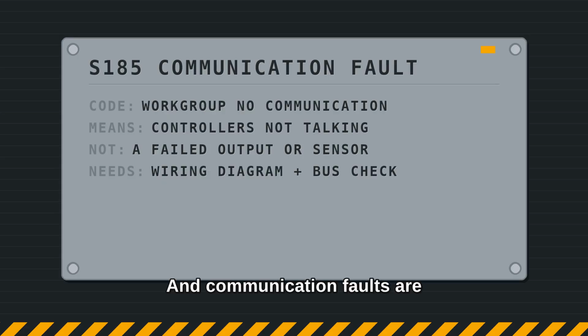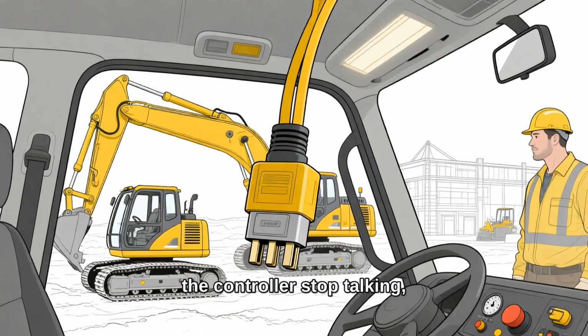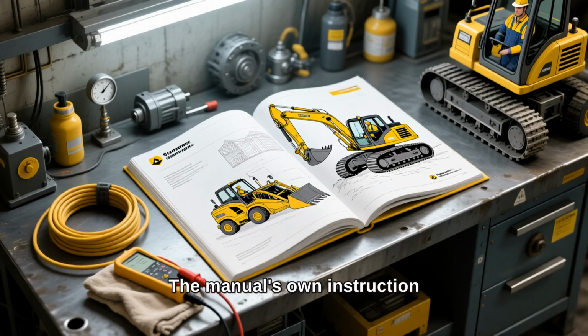And communication faults are their own country. The factory table lists workgroup no communication as a code by itself. When the panels and the controller stop talking, you're not testing a solenoid anymore. You're testing a network. The manual's own instruction at that point is to go to the electrical system service manual.